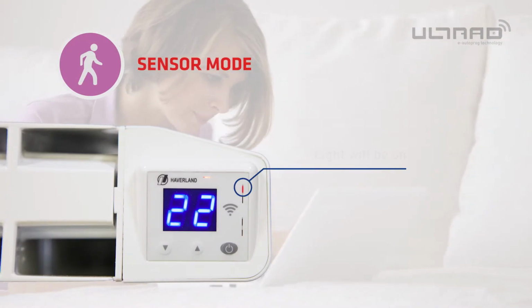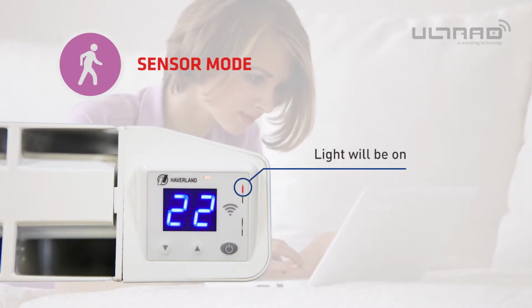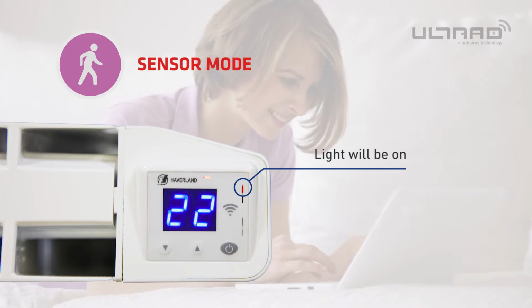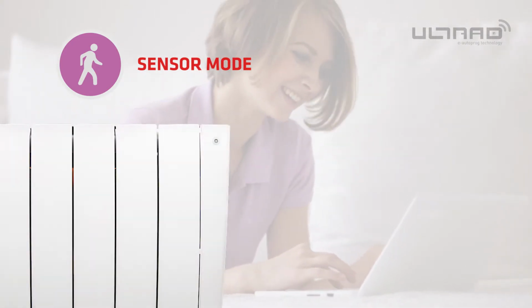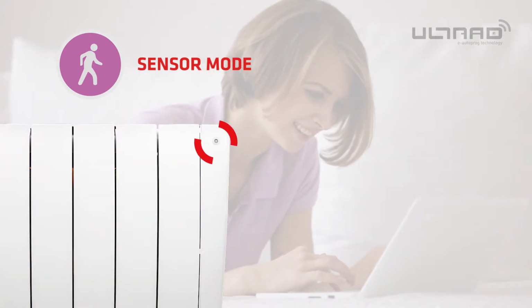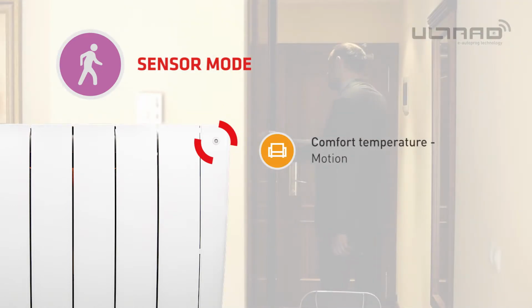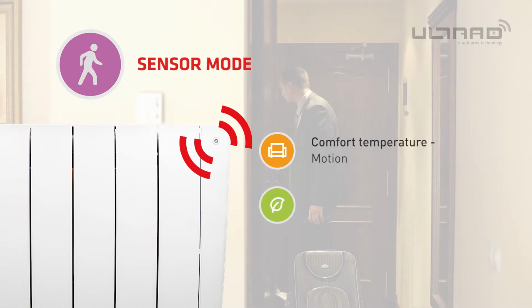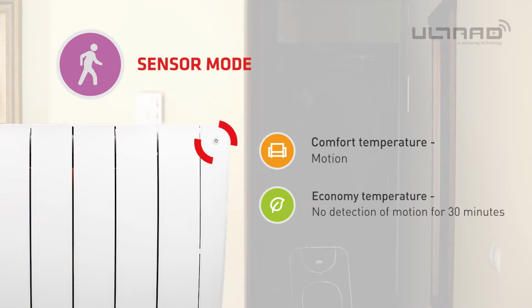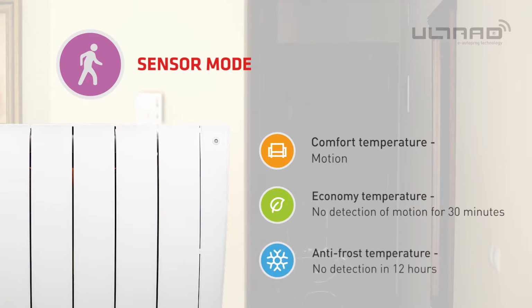Once on sensor mode, the ULTRAD will use its presence detector to determine which temperature profile to select. This mode will not save or learn any information about your lifestyle. If ULTRAD senses motion in the room, it will set to the comfort temperature. If there is no detection for 30 minutes, it will then change to economy temperature. After 12 hours, the ULTRAD will then change to anti-frost temperature.